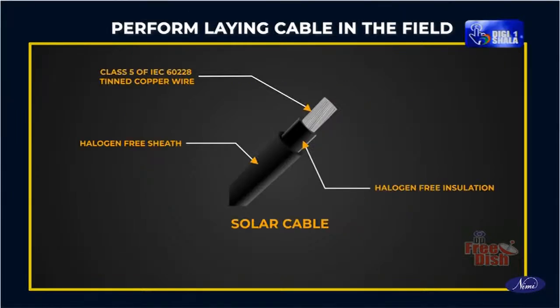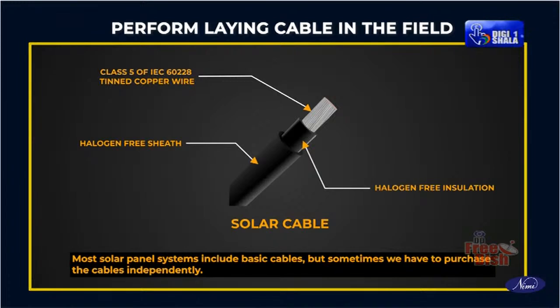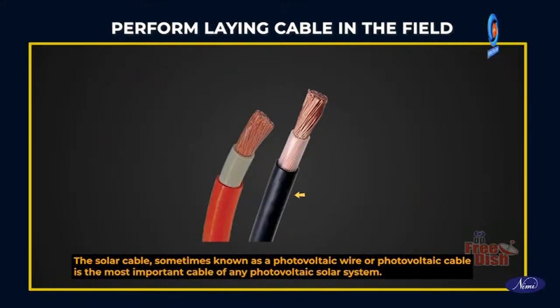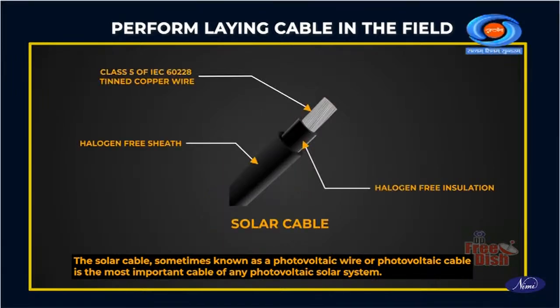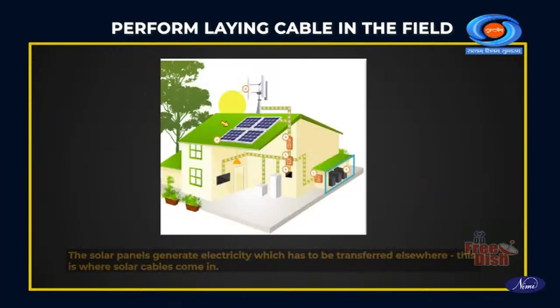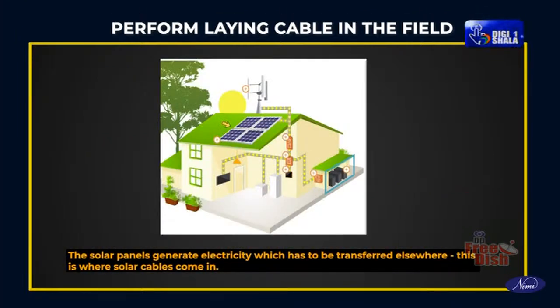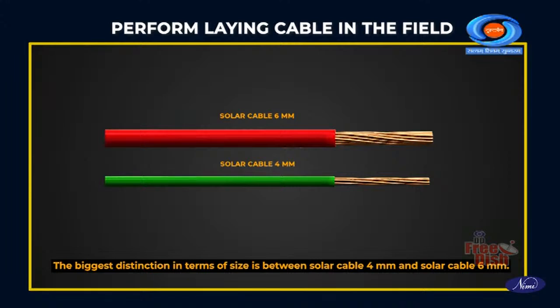Perform laying cables in the field. Most solar systems include basic cables, but sometimes we have to purchase the cables independently. The solar cable, sometimes known as photovoltaic wire or photovoltaic cable, is the most important cable of any photovoltaic solar system. The solar panels generate electricity which has to be transferred elsewhere. This is where solar cables come in. The biggest distinction in terms of size is between solar cable 4 mm and solar cable 6 mm.